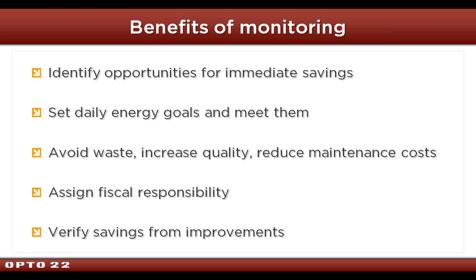Servicemen, people with no incentive, they didn't really have the training, they jumpered things to run continuously, they changed set points, they turned equipment off and on. Ben Orchard out at Opto, and I've talked about this a lot, was involved with running 2 hospitals in Australia, and every time I say that, he says, "Oh, you're exactly right." It's the people. It's every day trying to track. Good instrumentation will show you when there's a change. It'll show you when something's happened. We had phone dialers set up in the old days to call us when something went bad.